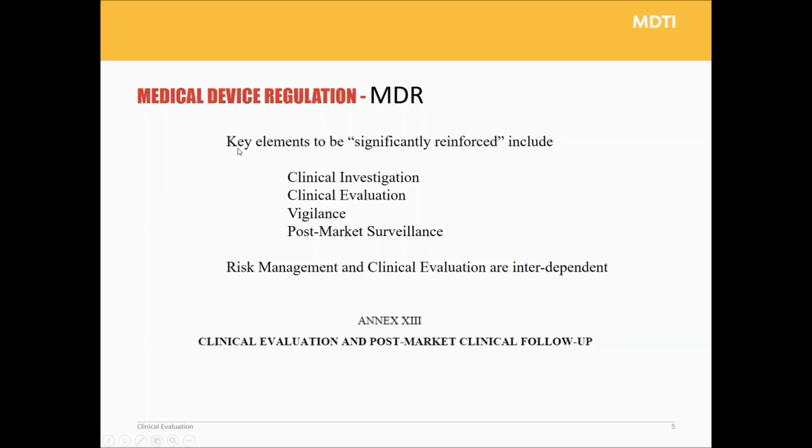So the key elements in the new MDRs, which are to be significantly reinforced as far as clinical is concerned, include clinical investigation, clinical evaluation, vigilance, and post-market surveillance.